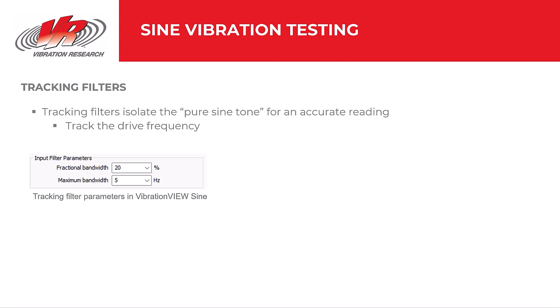Engineers employ tracking filters to isolate the pure sine tone so the controller can get an accurate amplitude reading at each frequency. Tracking filters are named as such because they track the center frequency. When the controller sweeps up or down, the filter moves with the sweep and only considers the frequency at which the test is running. Applying tracking filters is necessary because we want to control our sine test at the defined amplitude without influence from external factors.